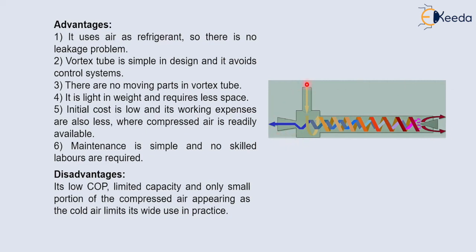In this figure, you can see the compressed air coming in and flowing like a vortex. Through the inner wall it gains heat and moves at very high speed. Some amount of hot air is exhausted from the hot side chamber. Through the control valve, some air is sent back at lower speed, flowing in the opposite direction in a second vortex. This lower speed air transfers its heat to the outgoing hot air, resulting in very cold air on the cold side.